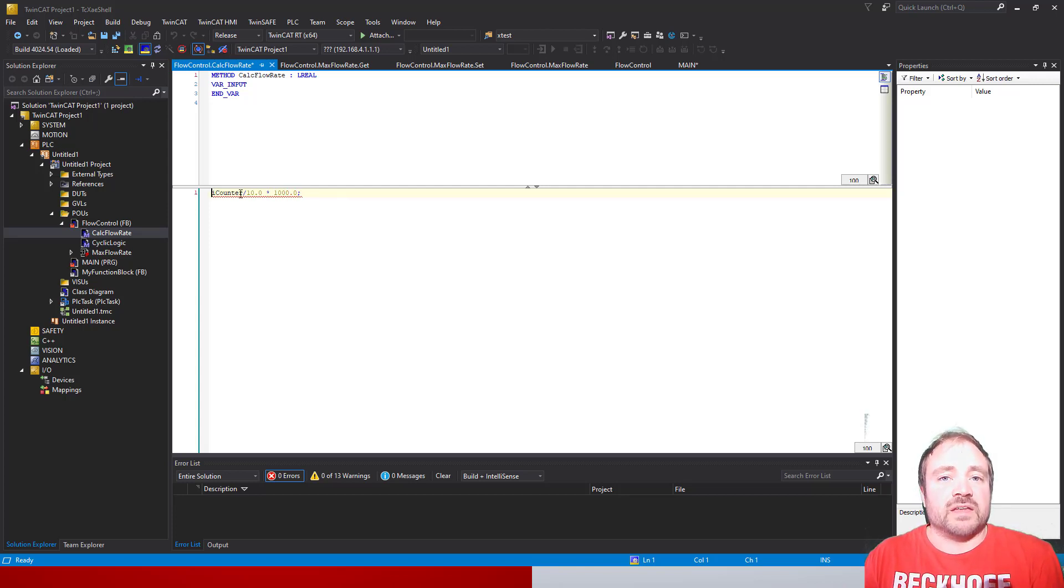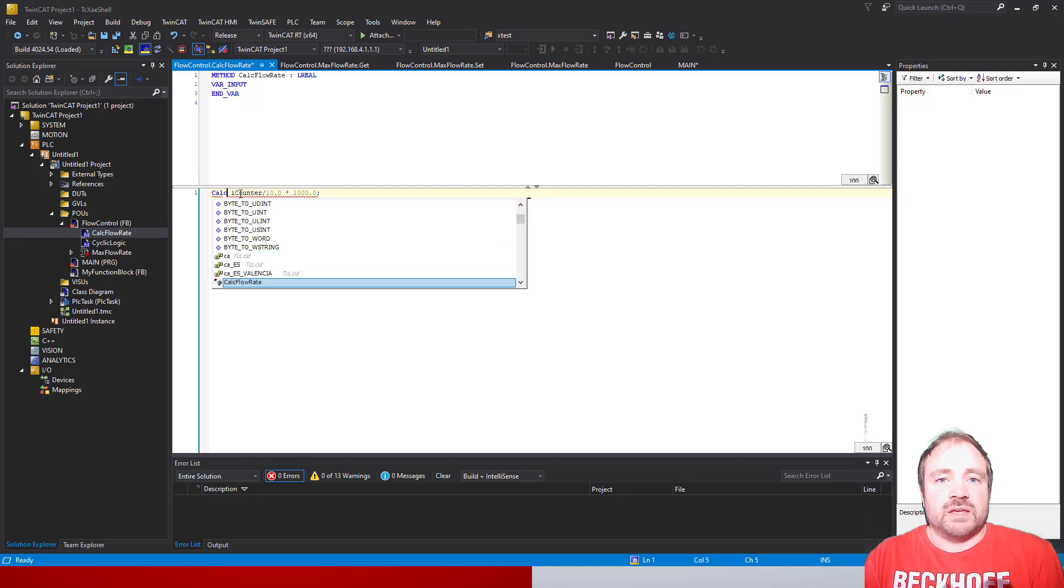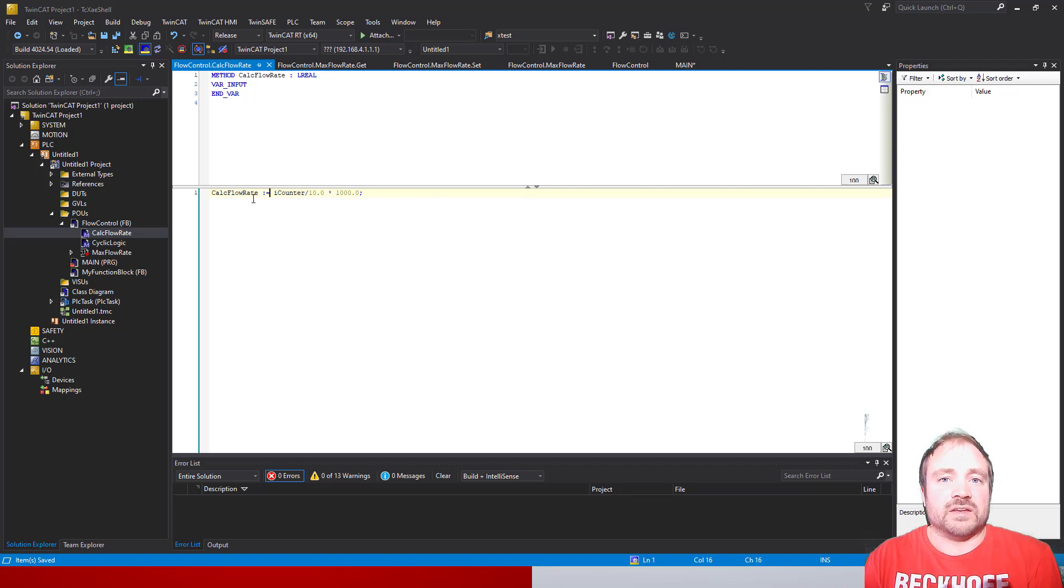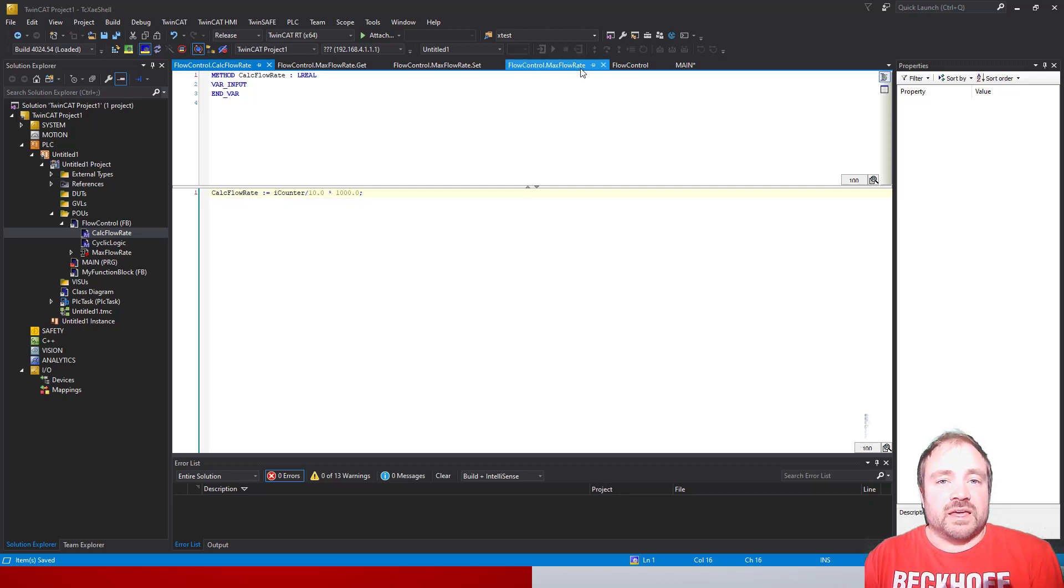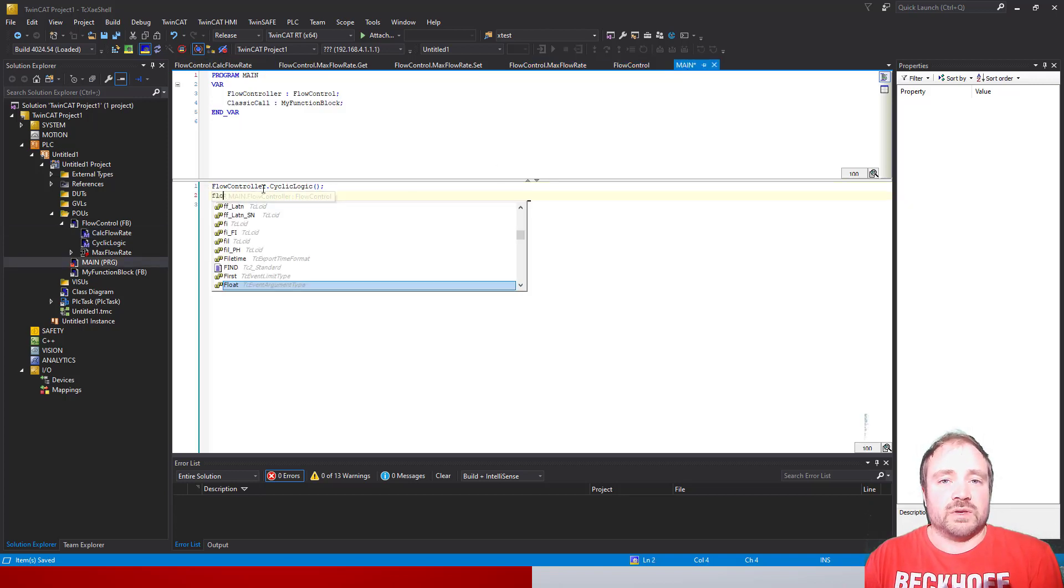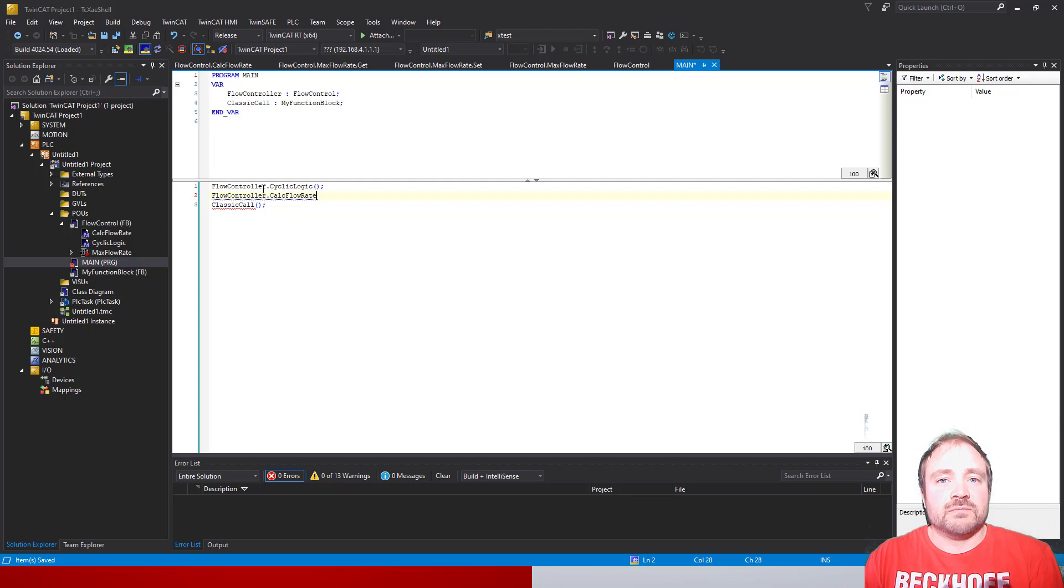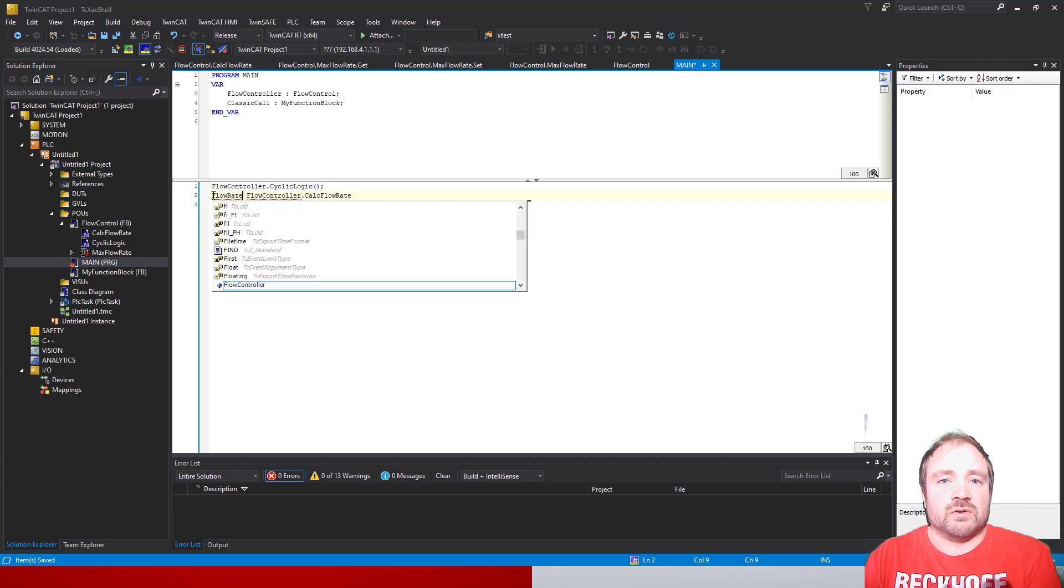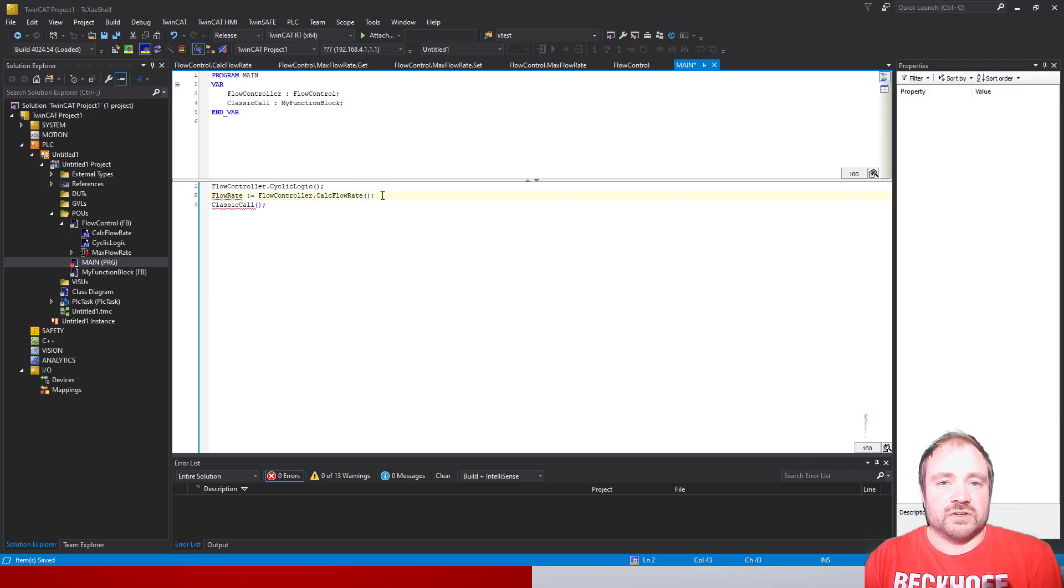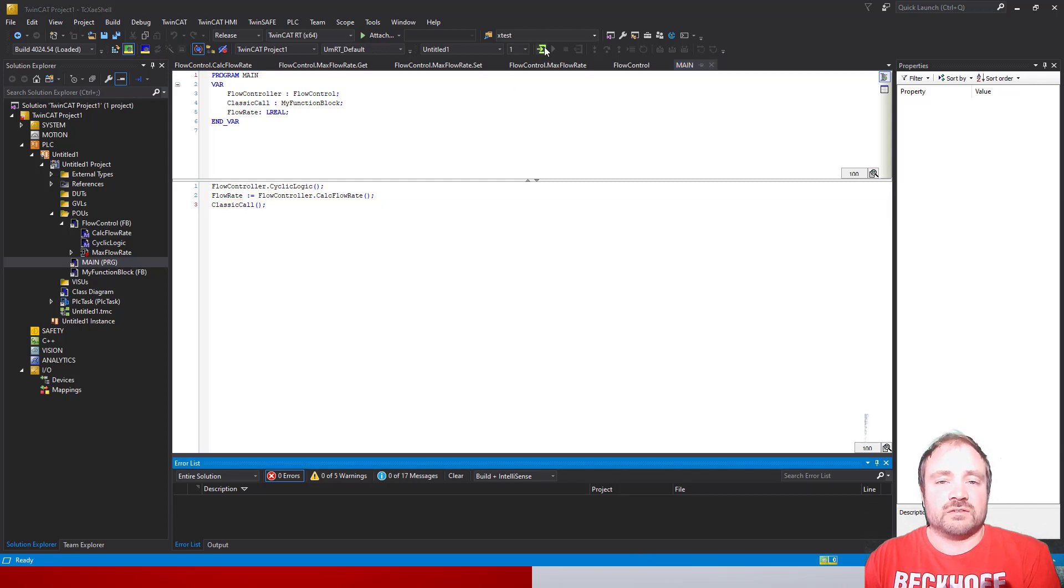Once we've done that, that's the method complete. All we need to do is call the method name, which is CalcFlowRate, and set that equal to the value that we calculate, and that will then return this so we're actually getting a value back. Just like the property, that means it's already available in the main. We can jump back to our main and we can create a variable called FlowRate of type LREAL, and we can set that equal to the return value of the method which we call by typing FlowController dot, just like the cycle logic one, dot CalcFlowRate open close brackets.